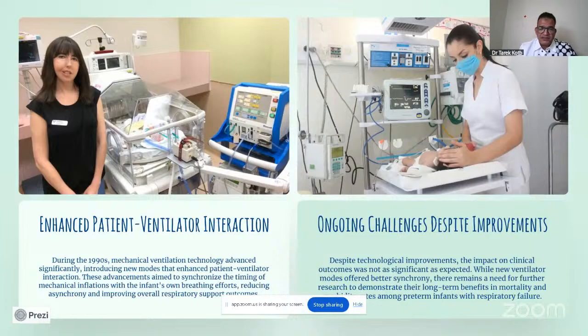Now we have synchronized ventilation and targeted tidal volume ventilation. Also, if you work with NAVA ventilation, which is neurally adjusted, the sensor is put in the esophagus very close to the diaphragm, and the idea is to sense the movement of the diaphragm to do the best trigger with the patient's inspiration. This improves the outcome, decreasing BPD and decreasing the length of stay on the ventilator. So now synchronization and triggering is the best thing that we can do.